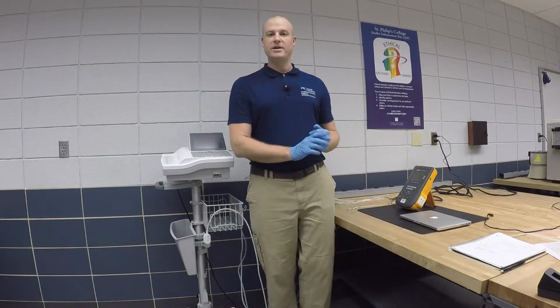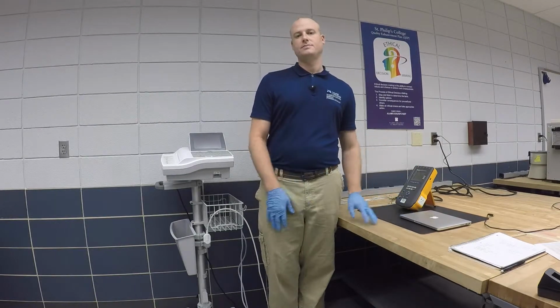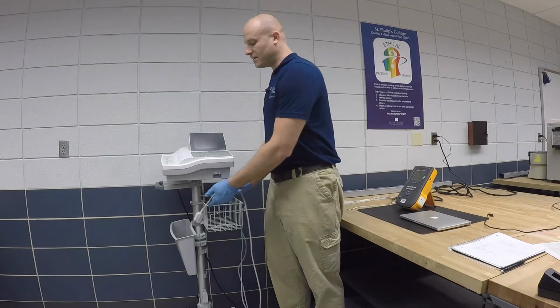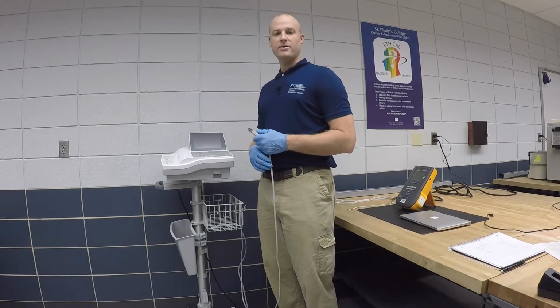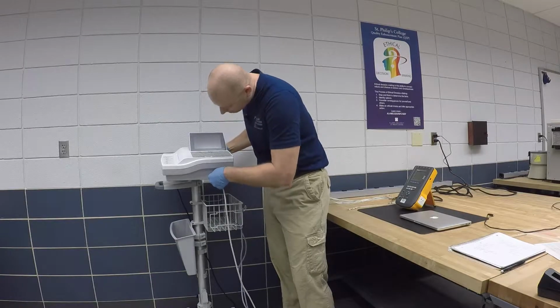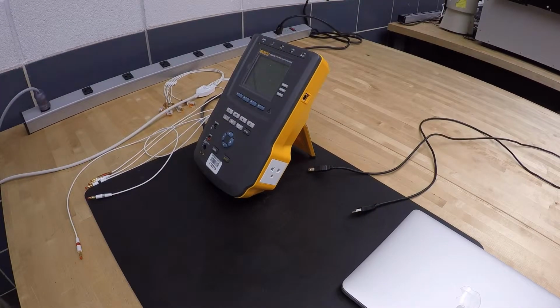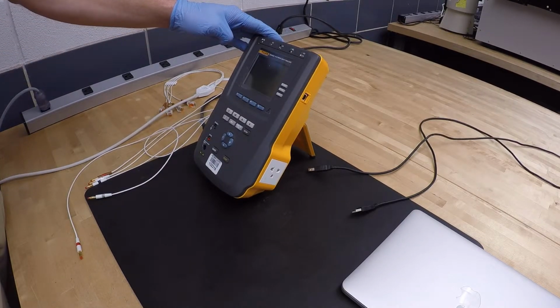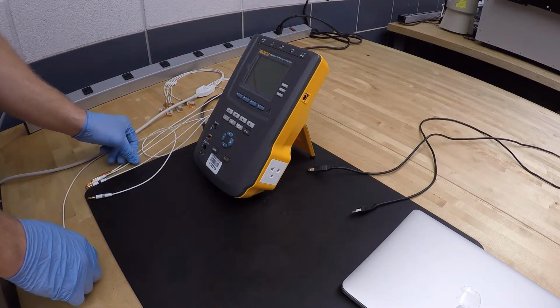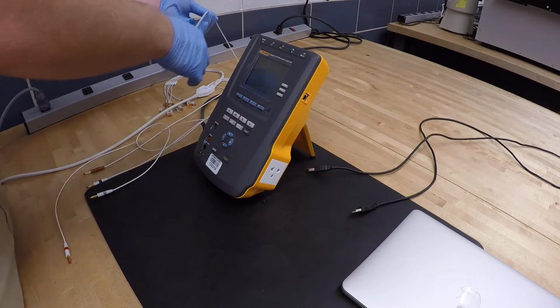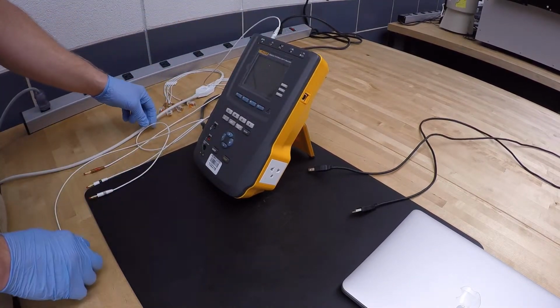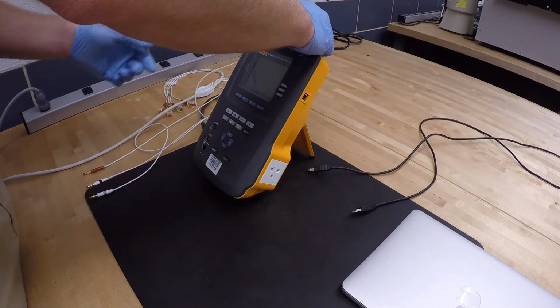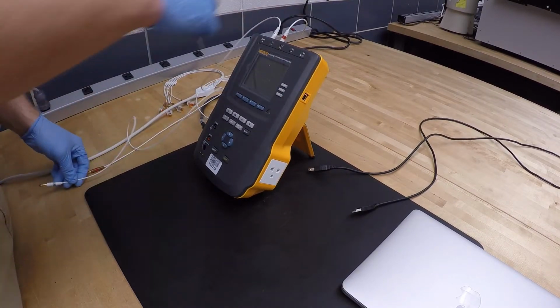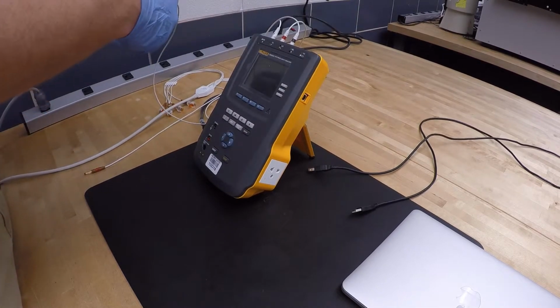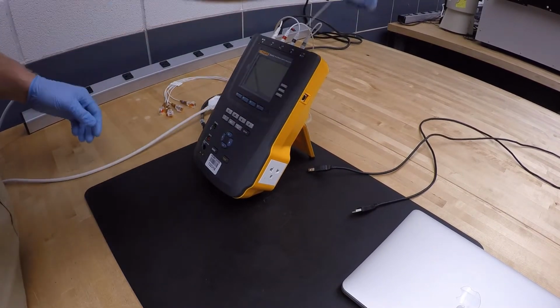To do this, we will now bring in our Fluke safety analyzer and computer. The first step of this is plugging the ECG leads cable into the electrocardiograph. To set up the safety analyzer, we're going to be plugging 5 ECG leads into the ECG ports on top of the device. We'll be using RA for right arm, LL for left leg, LA for left arm, RL for right leg, and V1.